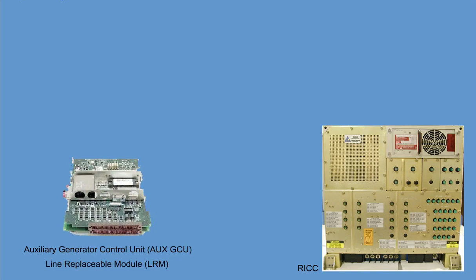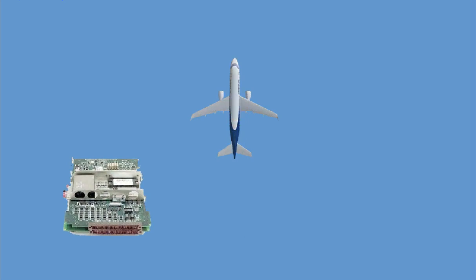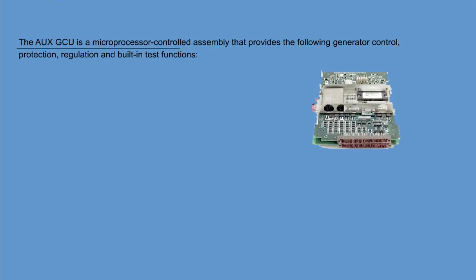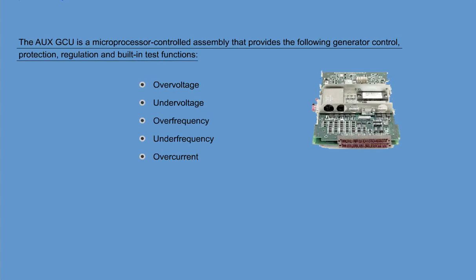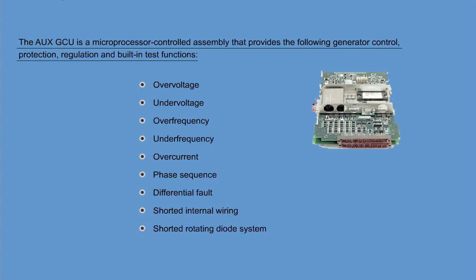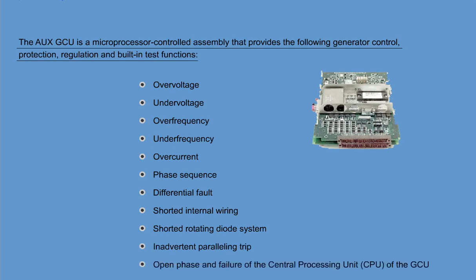The auxiliary generator control unit is a line replaceable module, LRM, and is located in the Right Integrated Control Center, RICC. The auxiliary GCU is a microprocessor-controlled assembly that provides the following generator control, protection, regulation, and built-in test functions: overvoltage, undervoltage; over frequency, under frequency; over current; phase sequence; differential fault; shorted internal wiring; shorted rotating diode system; inadvertent paralleling trip; open phase, and failure of the central processing unit of the GCU.